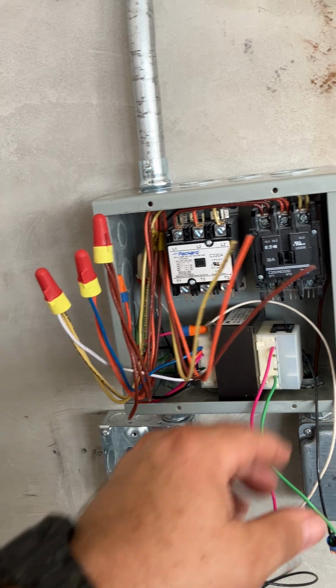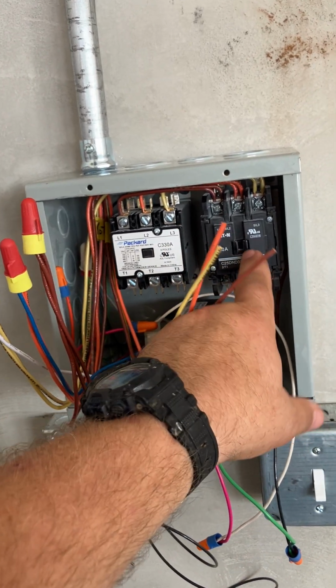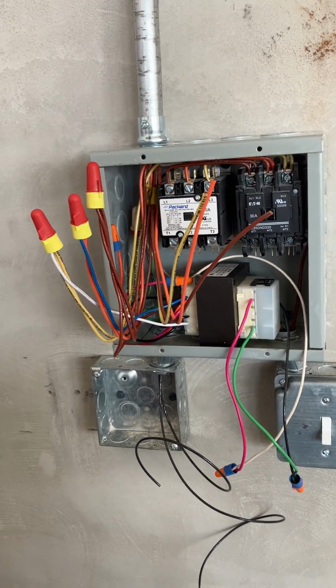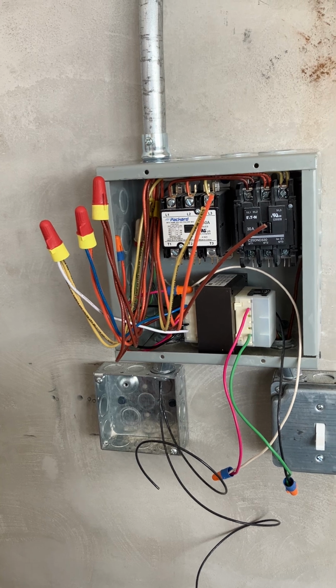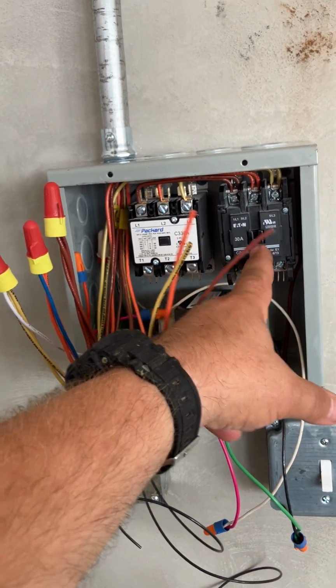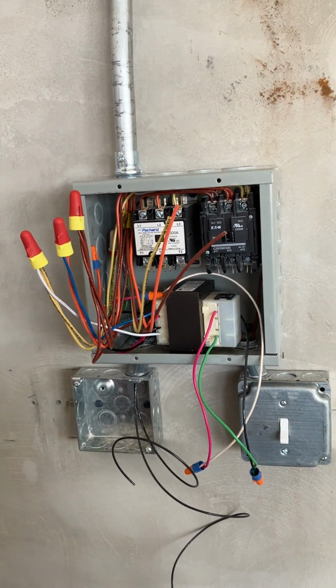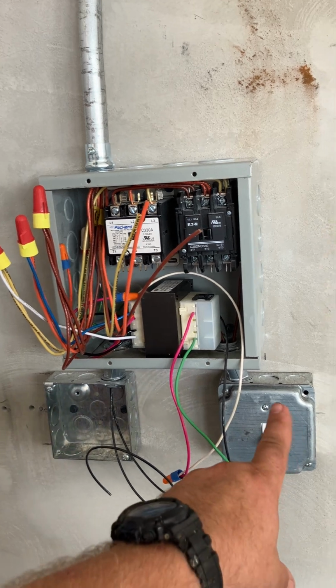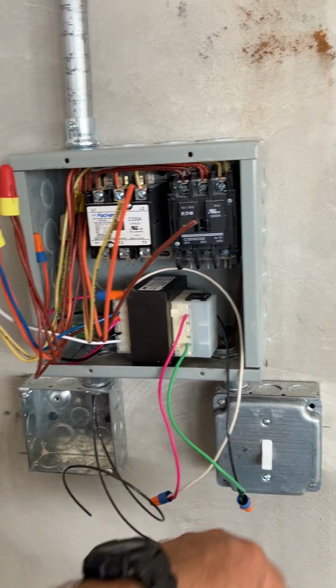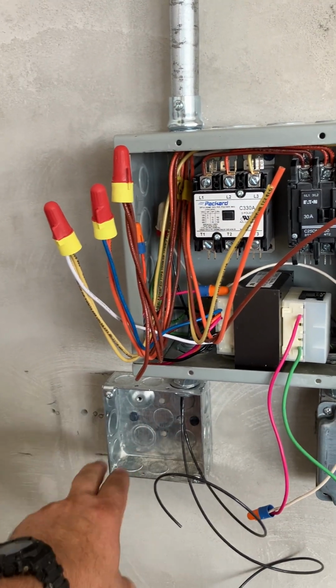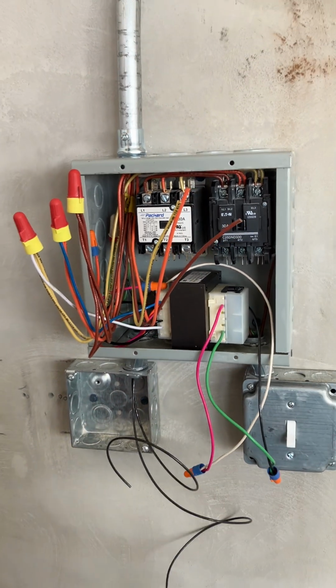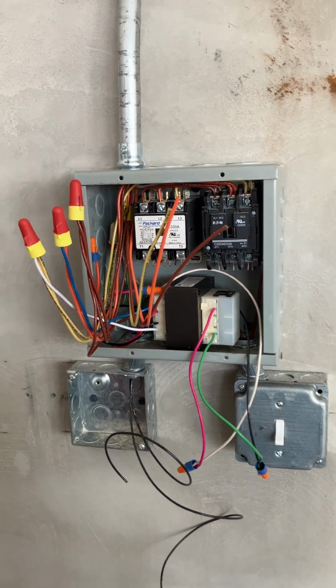Get rid of quite a bit of stuff in there and need only the 277 volt coil 3-pole contactor here to control those exhaust fans from two different switches: toggle switch, which is manual, and thermostat, which is automatic.